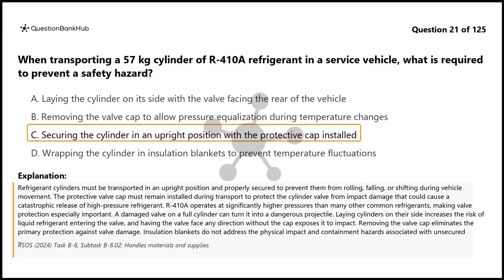Laying cylinders on their side increases the risk of liquid refrigerant entering the valve, and having the valve face any direction without the cap exposes it to impact. Removing the valve cap eliminates the primary protection against valve damage. Insulation blankets do not address the physical impact and containment hazards associated with unsecured cylinder transport.